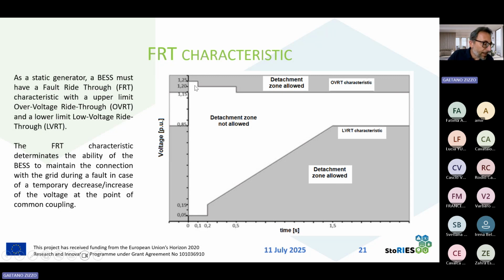Now see the upper part of this figure. We see that the voltage that the storage system can tolerate when we have a return overvoltage after the clearance of the fault can reach 125% of the rated voltage. In this case, this voltage can be tolerated for 100 milliseconds. Then, if the overvoltage is longer than this time, the overvoltage that can be tolerated is reduced, and then we reach the maintenance value, the allowed value of 115%.